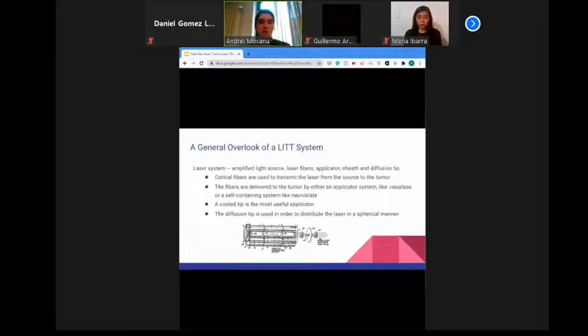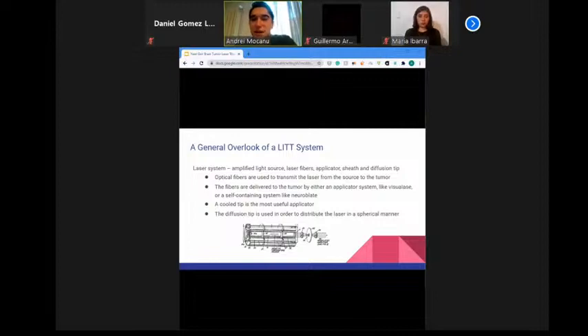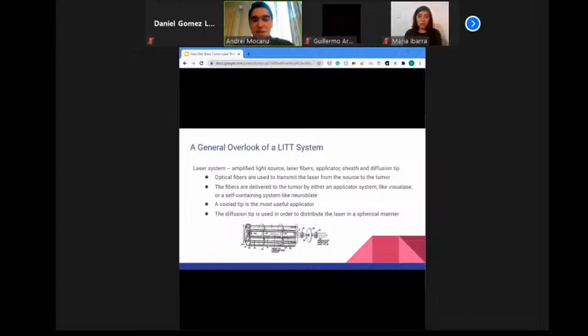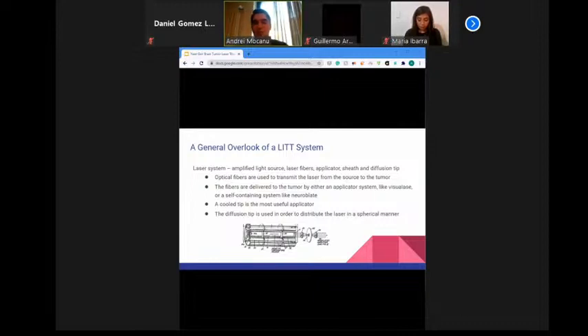A LITT system comprises a laser system, a workstation, and an MRI. The laser system includes a laser light source, laser fiber applicator, sheath, and diffusion tip. Laser is generated by the source and transmitted through optical fibers to the tumor. During transmission, part of the energy can be lost and absorbed by the transmitting fibers, which can eventually damage them.